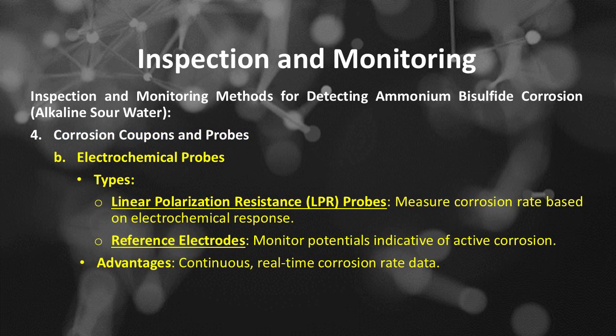Number B is electrochemical probes. The types of electrochemical probes include linear polarization resistance, LPR, probes, which measure corrosion rate based on electrochemical response, and reference electrodes, which monitor potentials indicative of active corrosion. The advantage of electrochemical probes is continuous, real-time corrosion rate data.